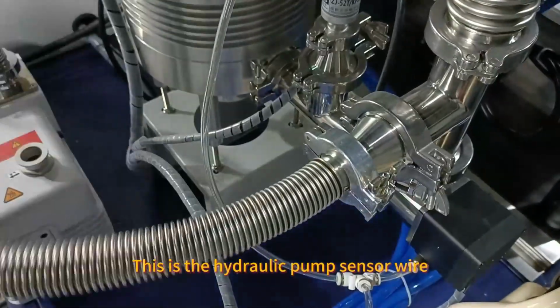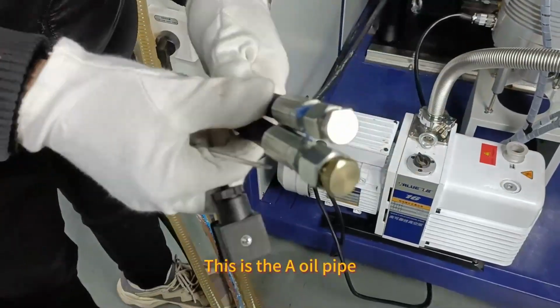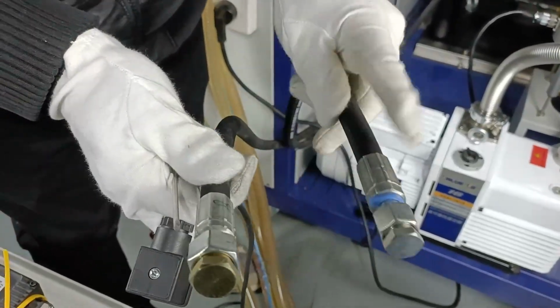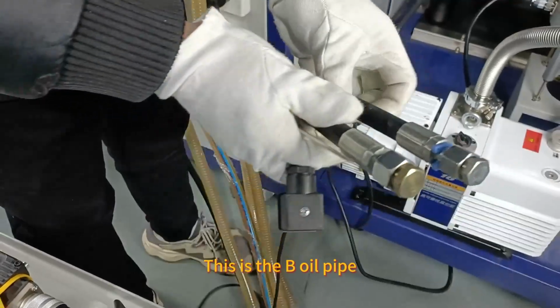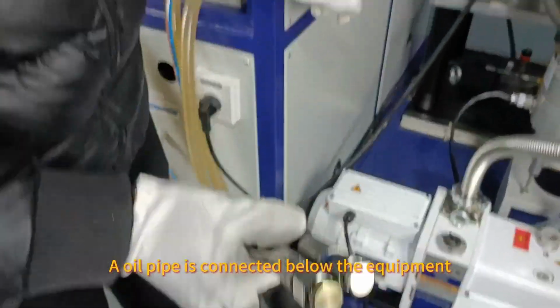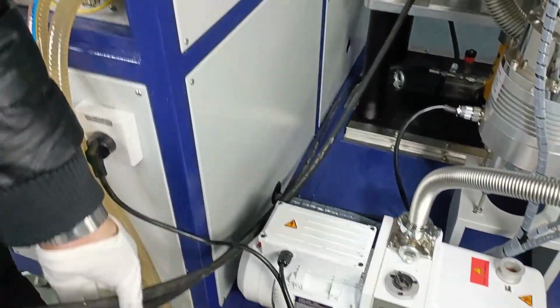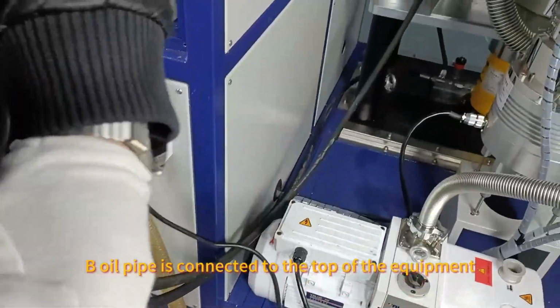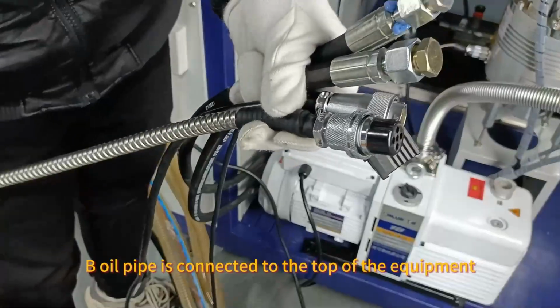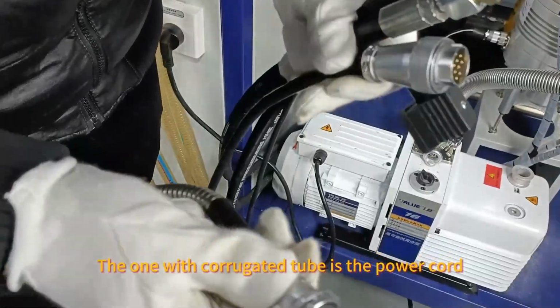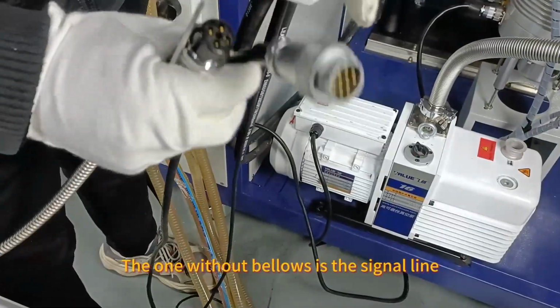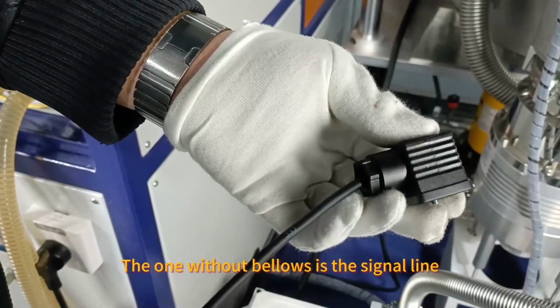This is the hydraulic pump sensor wire. This is the A-oil pipe. This is the B-oil pipe. The A-oil pipe is connected below the equipment. The B-oil pipe is connected to the top of the equipment. The one with the corrugated tube is the power cord. The one without bellows is the signal line.